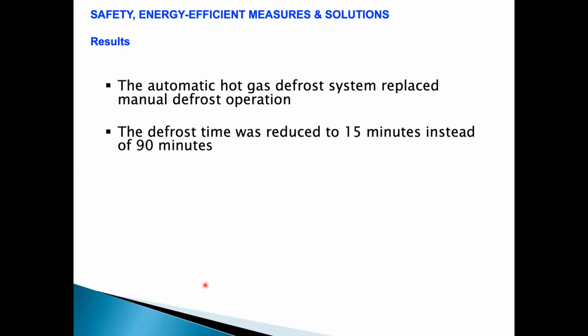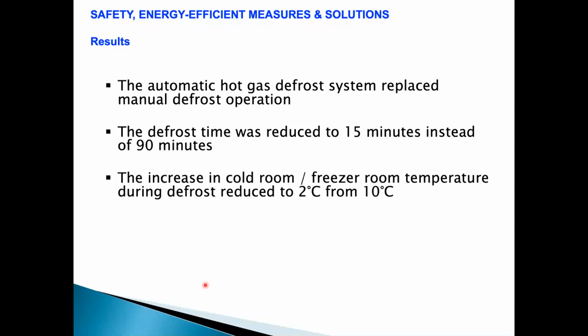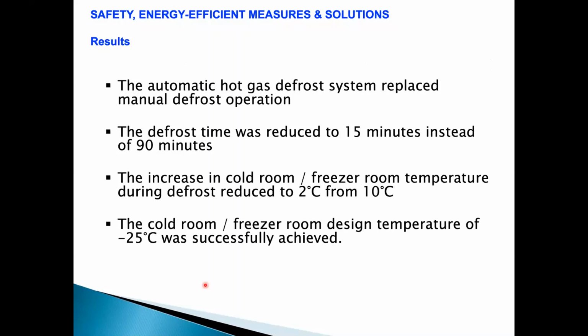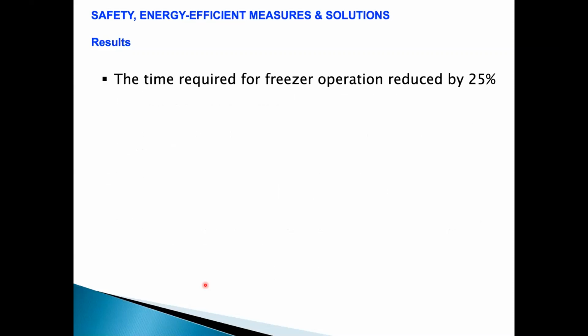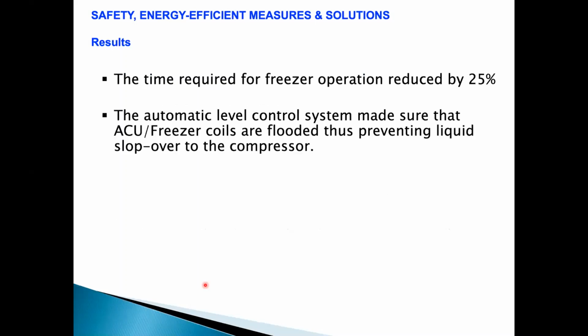With the automatic hot gas system, as I told you, the defrosting time was reduced from 1.5 hours to 15 minutes. The increase in room temperature during defrost was limited to 2 degrees. So from minus 30, it used to rise only up to minus 25, it may rise to minus 24, 23, and again it can be brought down very easily. The most important thing, which was the requirement of the customer, was achieved: minus 25 degree room temperature. They were no longer at minus 14. Because of appropriately maintaining the temperatures and defrosting on time, the humidity inside the room was reduced. Freezing operation time reduced by 25%. So overall production capacity increased, and there is also a reduction in power consumption.